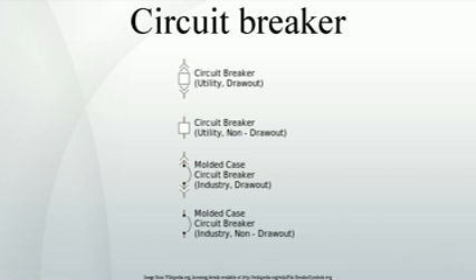Contacts are made of copper or copper alloys, silver alloys and other highly conductive materials. Service life of the contacts is limited by the erosion of contact material due to arcing while interrupting the current. Miniature and molded case circuit breakers are usually discarded when the contacts have worn, but power circuit breakers and high-voltage circuit breakers have replaceable contacts.